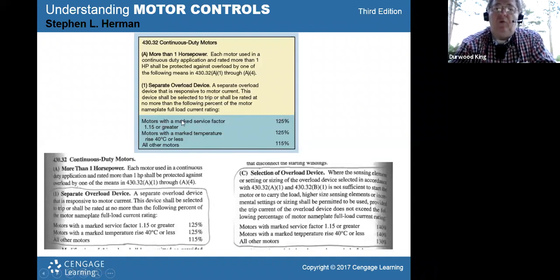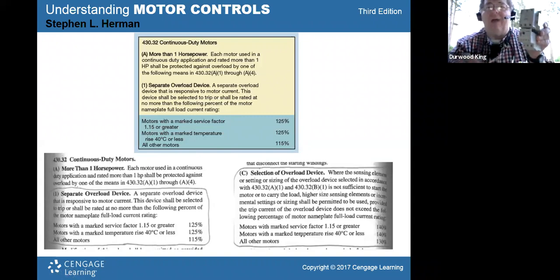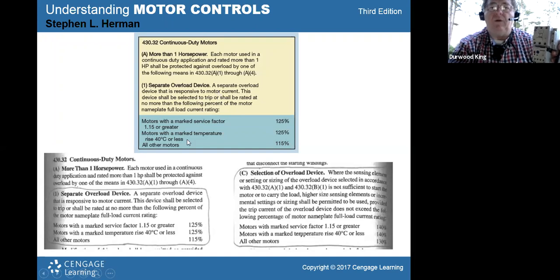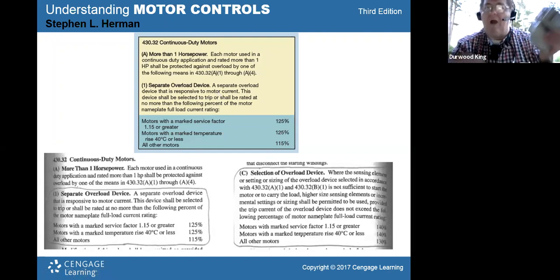But you use information of service factor. If your service factor meets that criteria on the nameplate, then you set your overload at 125% of your amp rating on the plate. Or if your temperature rise on the nameplate is 40 degrees C or less, you also figure your amp rating at 125% of your nameplate. So that tells you how to set the overload properly. Now, one thing that the book didn't get into, and I've included it in here, is this.